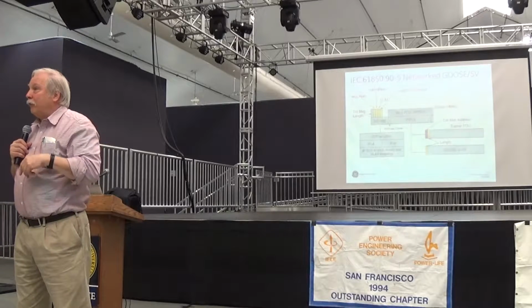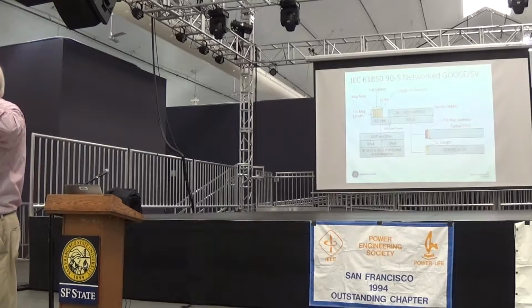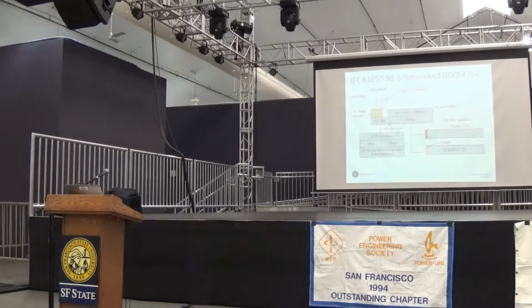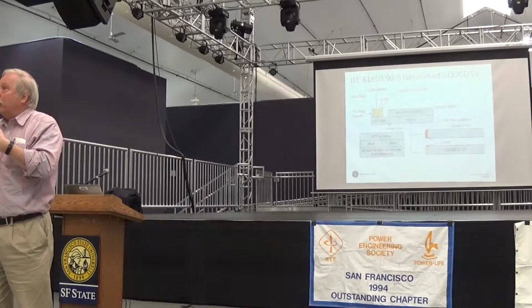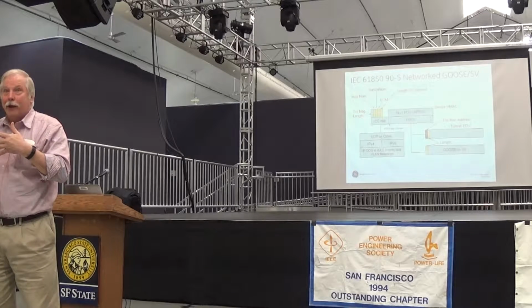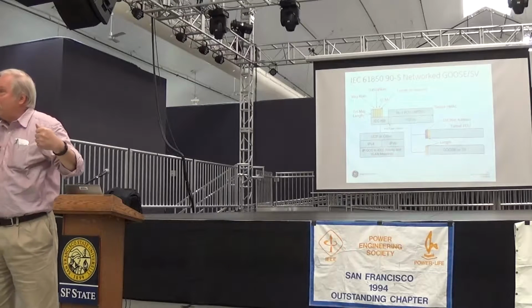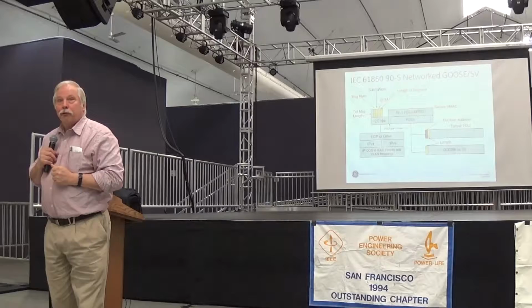These would be set points for output power. In a 4-quadrant inverter, by the way, 4-quadrant means not only can I regulate VARs, I can regulate power flow, either plus or minus power flow. This will happen as solar inverters are integrated with battery storage systems in the home or wherever they're located. So that means I can either take energy from the battery or put energy into the battery from the solar inverter.